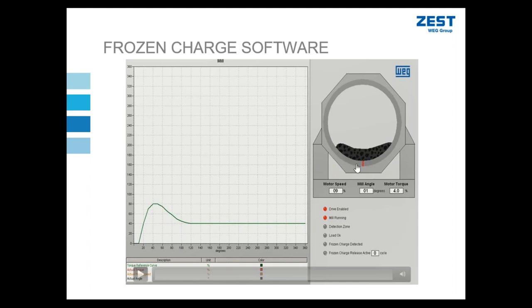If a mill has a frozen charge, in other words, if the material is stuck to the side of the mill and it goes beyond a certain angle where cascading should start to occur, that frozen charge can fall and damage the linings of the mill. So it is quite valuable if the VSD can detect it. We do that by monitoring torque. As our mill angle increases, if cascading does not occur inside the mill, it pretty much means that the mill torque will not start to drop off as expected. We can calculate that on the VSD, and within a certain range of that torque increasing, we can determine that there is a frozen charge and abort the start.